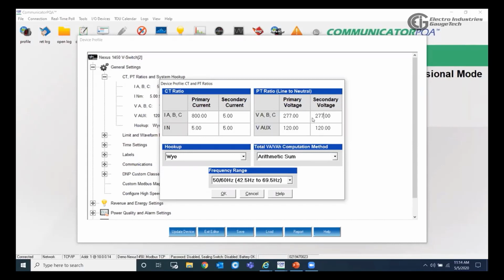And this is not going to affect the power and the energy reading. But it's very important to set the PT ratio according to the system voltage, because we have the limits and the alarm settings in this meter. And those limits and alarms would be a percentage of the full scale value, and that full scale value would be taken from this number. We will show that later. So I will set back to 120, 120.